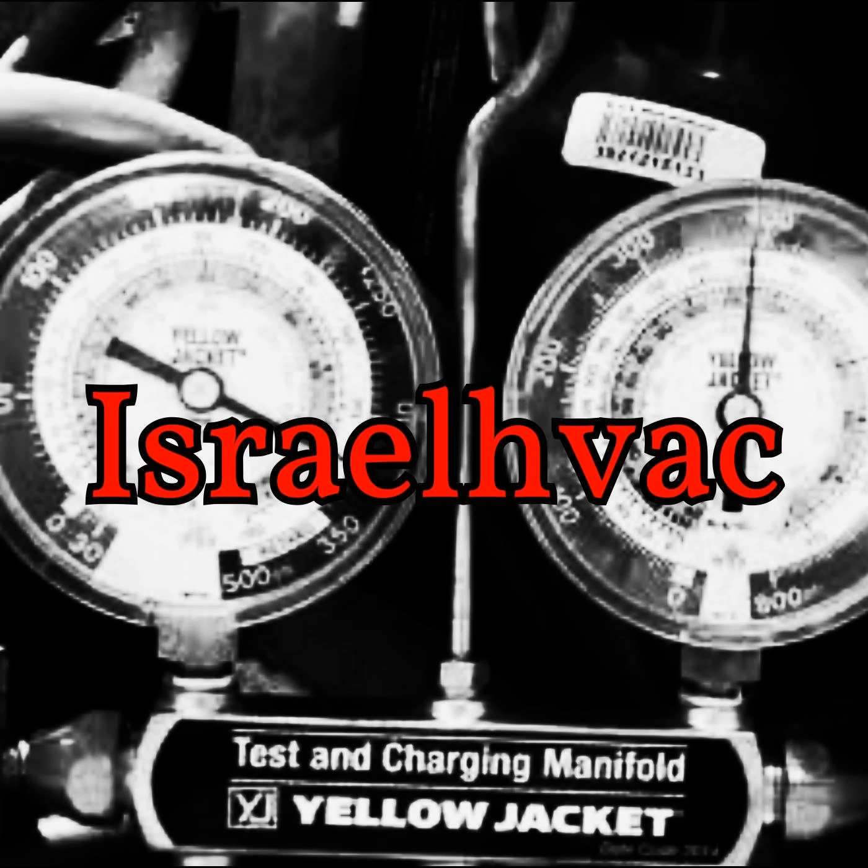But this particular guy from today, he wants a whole new system. He's got a 28-year-old Amana up in the attic. Wow. A 28-year-old coil where the primary pan is leaking water down into the secondary drain pan. So for him, a 407C unit is probably not a good idea because he's going to be changing his evap coil out pretty soon as well.